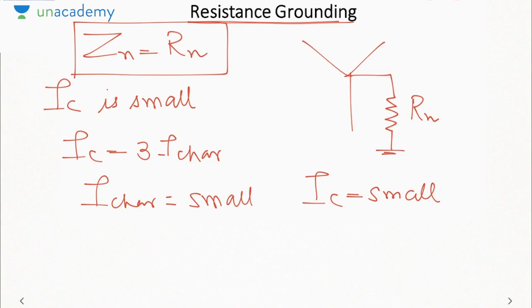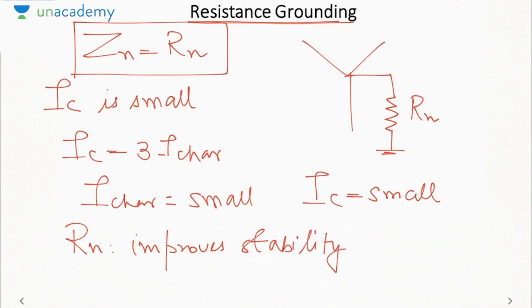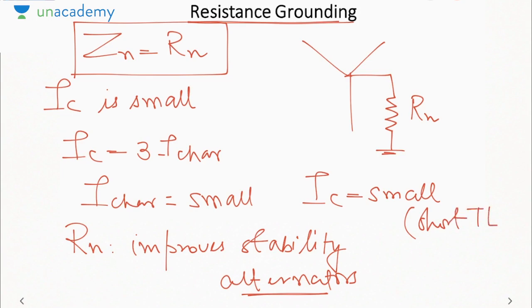But what happens is that, as we will study later on, Rn improves stability of a system. And in case of synchronous generator, which are mostly used in our power plant, stability is one of the most important criteria. That is why resistance grounding will be mostly used in case of alternators. It can only be used where the line charging current is small, like the case of short transmission line, because there we neglect the line charging current.